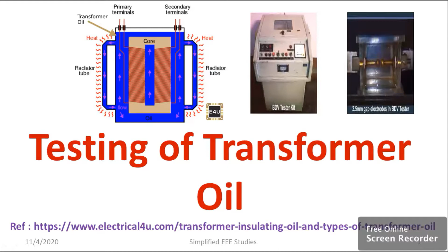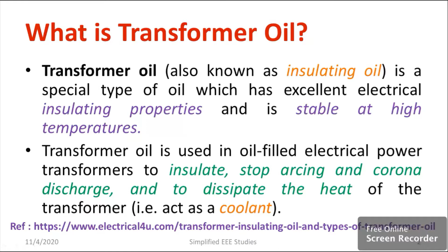Now let us understand the basics of transformer oil. Transformer oil, also known as insulating oil, is a special type of oil which has excellent electrical insulating properties and is stable at high temperature. That is a specialty - it can operate at very high temperature, and even at low temperature. Transformer oil is used in oil-filled electrical power transformers to insulate, stop arcing and corona discharge, and finally to dissipate heat towards the outside. Therefore, it acts as a coolant. It has a dual function: insulator and coolant. These are the basic information.